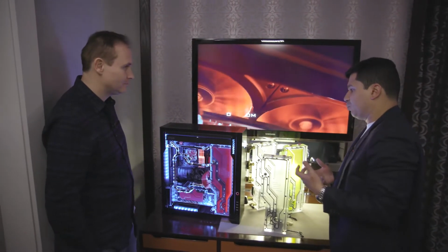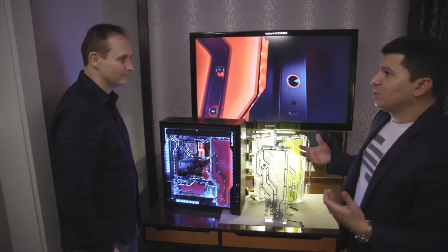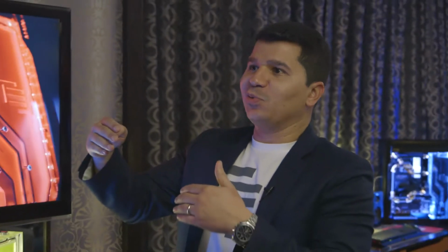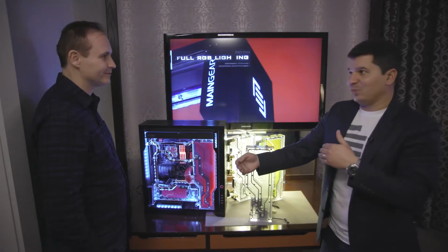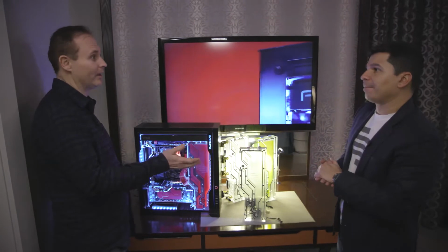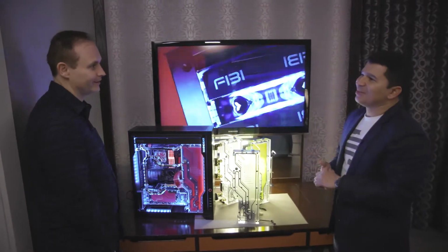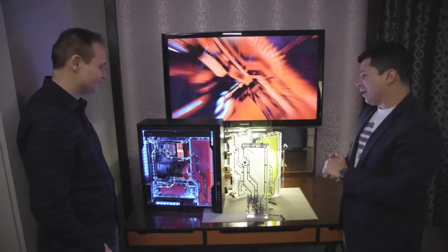What that means is it becomes more efficient. Typically, the CPU gets cool water, leaves warm, and goes warm to the first GPU, then gets even hotter by the time it hits the third GPU. That can impact overclocking, you can't clock as high, because your GPUs can only clock as high as the weakest link in the chain. In this case, we're able to throw fresh water into both heat sources. Yeah, that's really intelligent design.